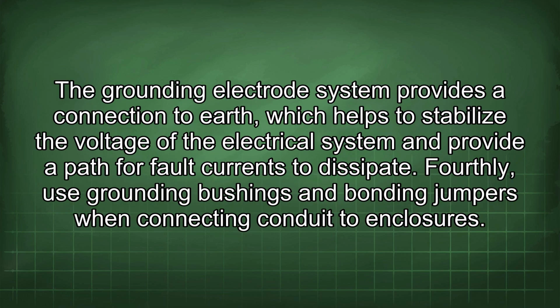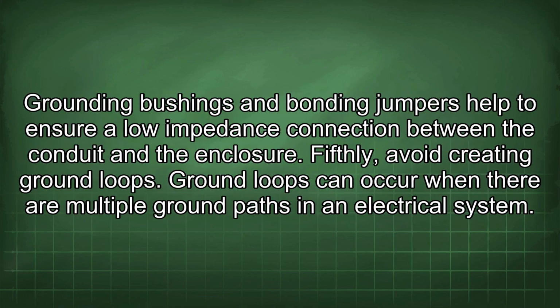The grounding electrode system provides a connection to earth, which helps to stabilize the voltage of the electrical system and provide a path for fault currents to dissipate. Fourthly, use grounding bushings and bonding jumpers when connecting conduit to enclosures. Grounding bushings and bonding jumpers help to ensure a low impedance connection between the conduit and the enclosure.